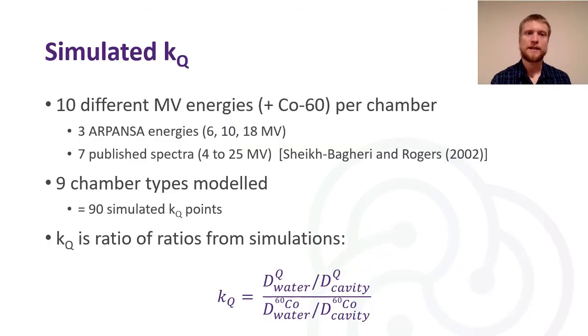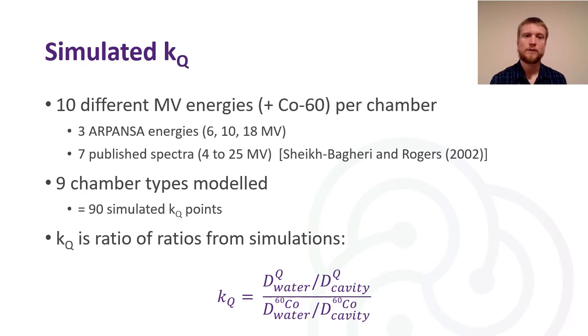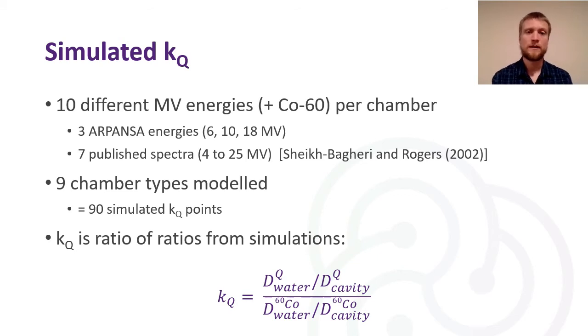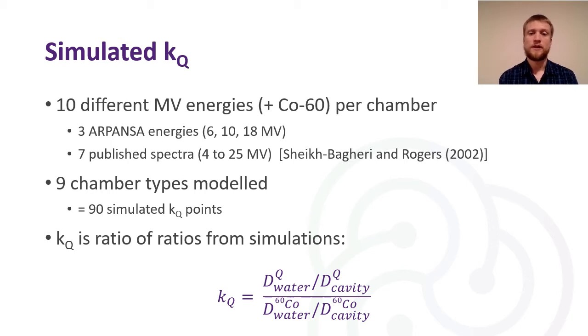For the simulated KQ values, we calculated 10 different MV energies plus Cobalt-60 for each chamber. These 10 come from three different ARPANSA energies in a full LINAC model — that's 6, 10, and 18 MV — as well as seven published spectra in a range of energies from 4 to 25 MV. We modelled nine different chamber types, so 10 different MV energies across nine chambers gives us 90 simulated KQ data points. The KQ value is the ratio of dose to water over dose to cavity in beam quality Q, divided by the dose to water over dose to cavity in Cobalt-60.